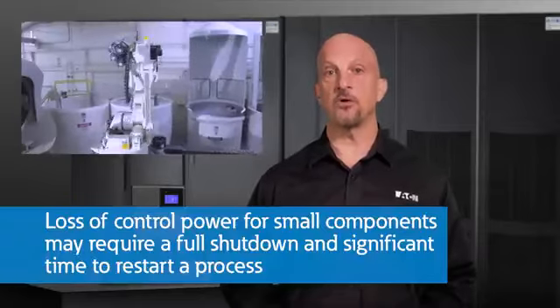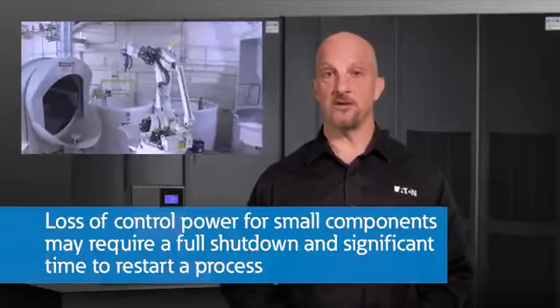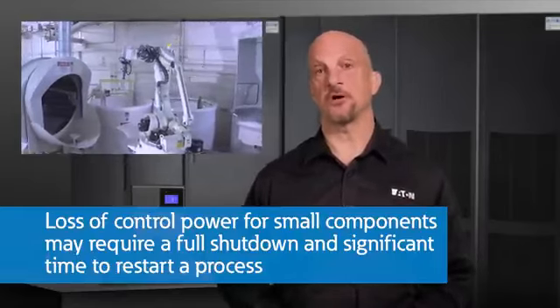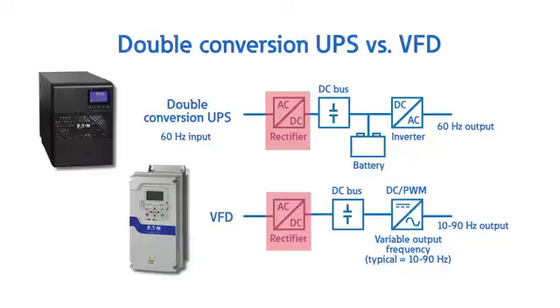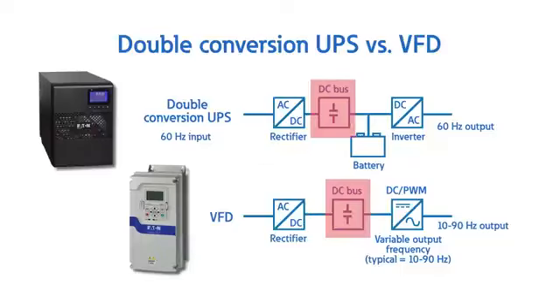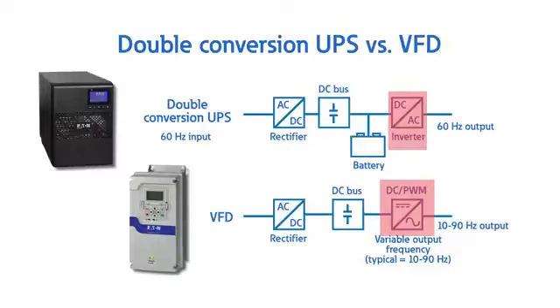In many of these applications, the loss of control power for small components requires a full shutdown and significant time to restart the process. To really understand the design and components of a double conversion or online UPS, we like to make the comparison with a variable frequency drive, or VFD. Both have a rectifier to convert from AC to DC. Both have a DC bus with a smoothing capacitor to minimize ripple, and both have an inverter to convert from DC back to AC. However, there are 2 main differences between a VFD and a UPS.